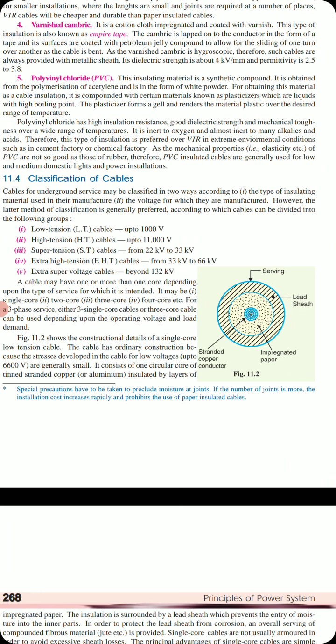According to this, the first one is low tension cable, up to 1000 volt, which we call LT cables. Second one is high tension cable, up to 11 kV or 11,000 volts, called HT cables. Next is super tension cables, from 22 kV to 33 kV, called ST cables. Then extra high tension cables from 33 kV to 66 kV, we call EHT cables, that is extra high tension. Then extra super voltage cables beyond 132 kV.